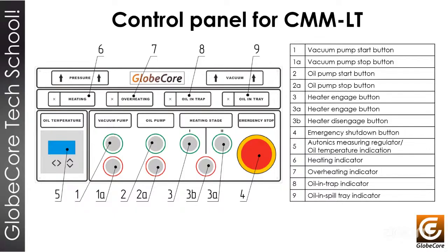You will have one button to start the vacuum pump and another button to turn off the vacuum pump. You will have one button to turn on the oil pump and one button to turn off the oil pump. Depending on the machine, you can have one or two stages of heating. If you have, like in this case, two different heating stages, you will have one button for stage 1, one button for stage 2, and one button to turn off the two heating stages of the thermo vacuum machine.